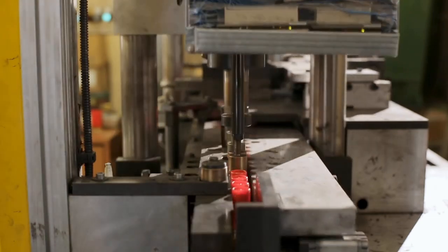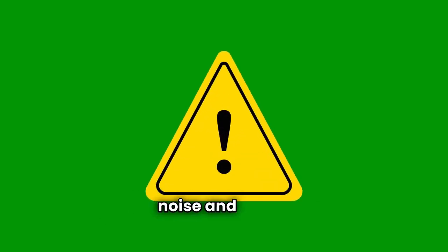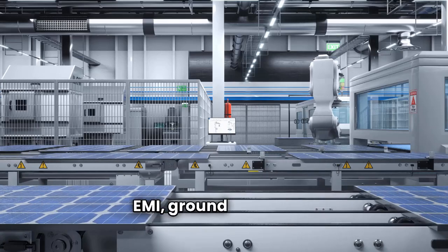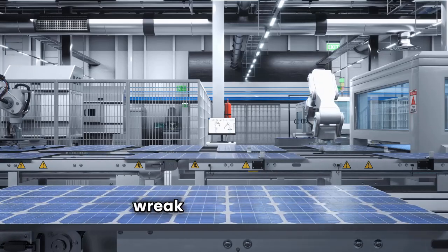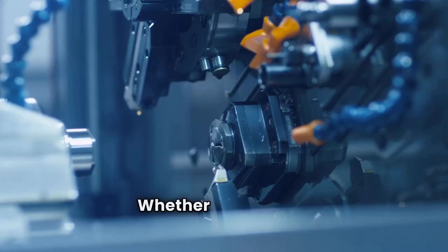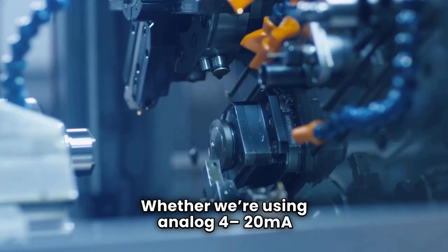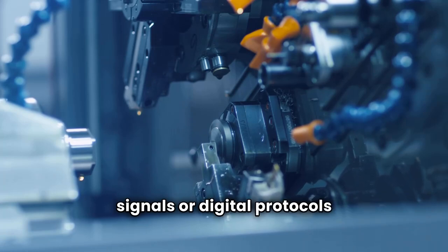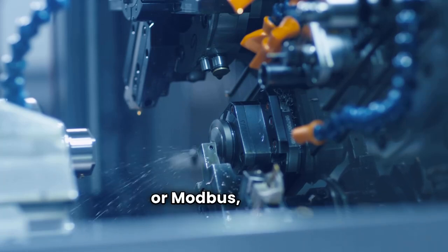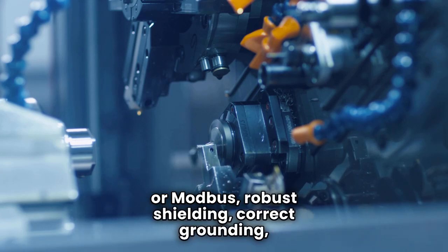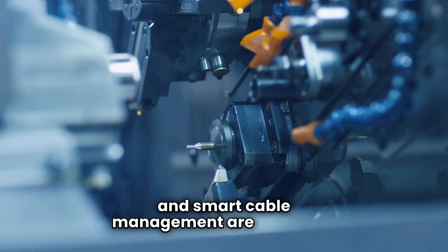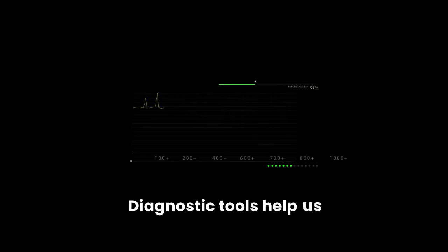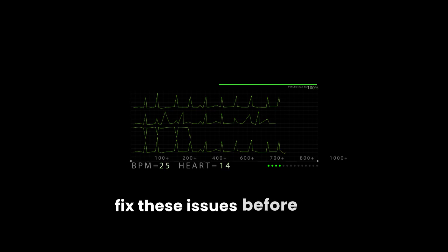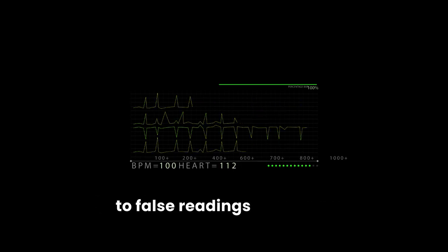instrumented systems. Then there's the issue of noise and signal interference. EMI, ground loops, and crosstalk can wreak havoc on signal integrity. Whether we're using analog 4-20mA signals or digital protocols like Profibus or Modbus, robust shielding, correct grounding, and smart cable management are essential.